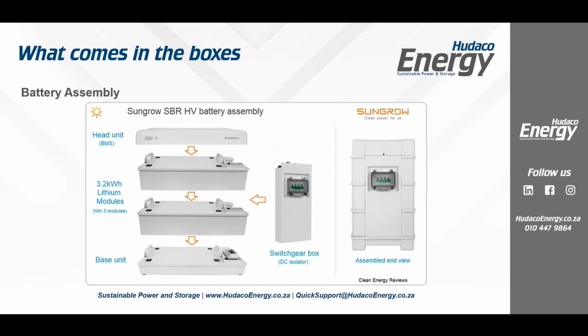Okay, so this is what it looks like. You would put your base down, you would drop on each one of your modules, then you slide your switchgear into the side, and that's what it looks like there in the side. Pop the top on, and then your cables will come out the back into trunking, and I normally use about 4 centimeter wide trunking. Some clients will use slightly bigger trunking if they want to. You could go up to 10 centimeter, 100 mil if you wanted to, but you're running what, 5-6 millimeter cables. So it's really not a lot.